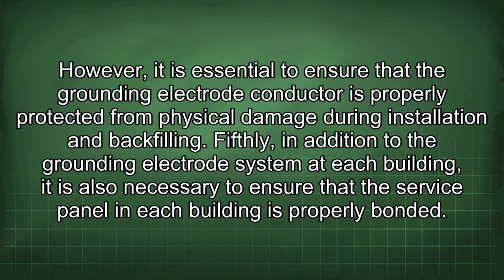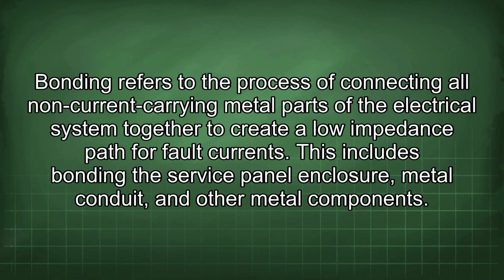backfilling. Fifthly, in addition to the grounding electrode system at each building, it is also necessary to ensure that the service panel in each building is properly bonded. Bonding refers to the process of connecting all non-current carrying metal parts of the electrical system together to create a low impedance path for fault currents. This includes bonding the service panel, enclosure, metal conduit, and other metal components.